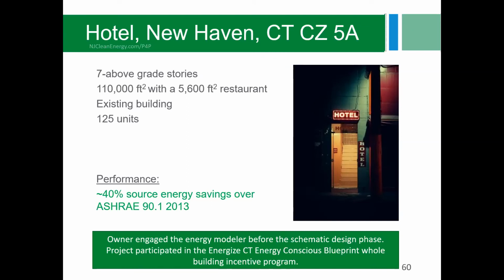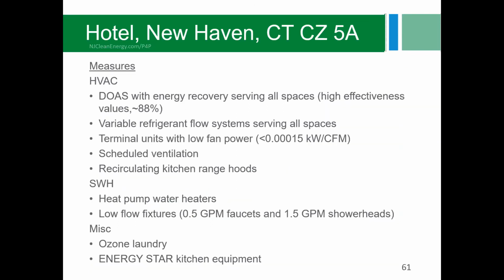So what were the design elements here? So these are the measures. It had a direct outside air unit with energy recovery serving all spaces in the building. And it had high effectiveness values, approximately 88% enthalpy effectiveness.